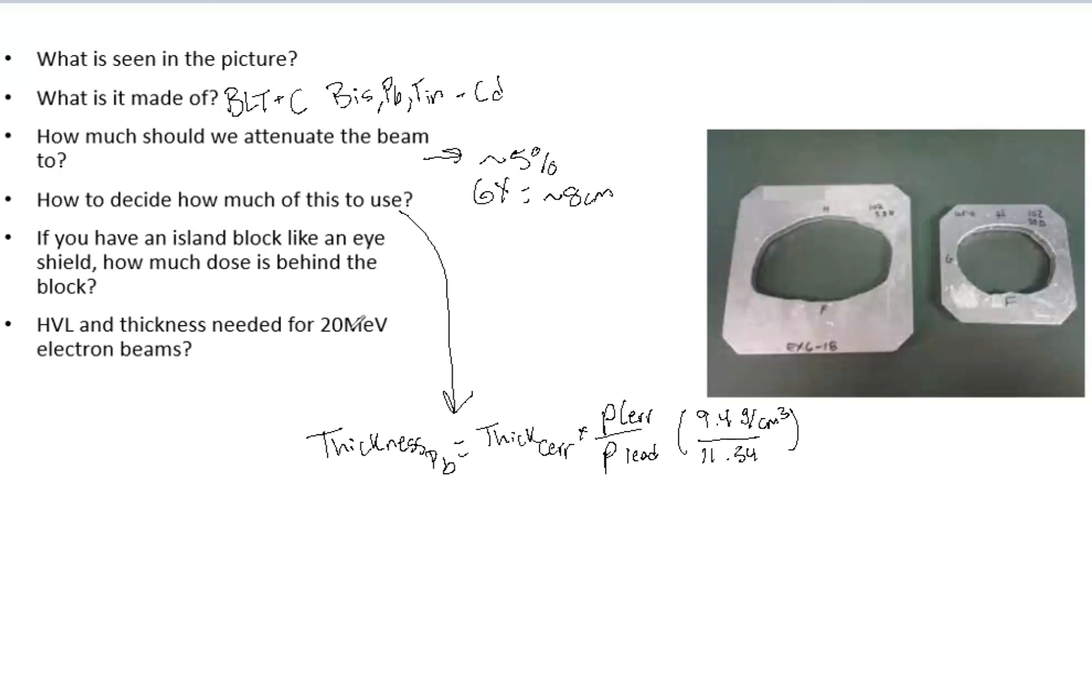If you have an island block, like an eye shield, this does happen in realistic medical physics in the clinic, how much dose is behind the block? So you remember, we are going to use this to block to about 5% past the shield or past the Cerrobend. But because it's an island block, you're going to have, imagine this block, you have a beam coming through, but you also have some radiation and some scatter that is going to get in behind that block. So the combination of the transmission through the block and the scatter is going to be about 20 to 30% compared to no block at all. So of course, this does depend on the size of the block, but that is a good number to remember if you are asked or quizzed about this.